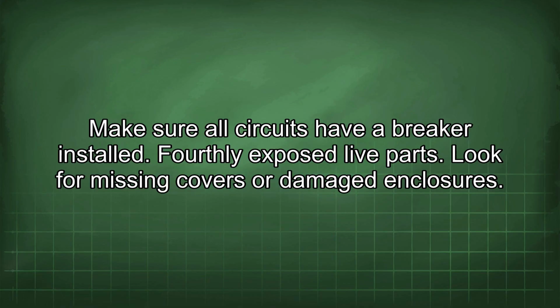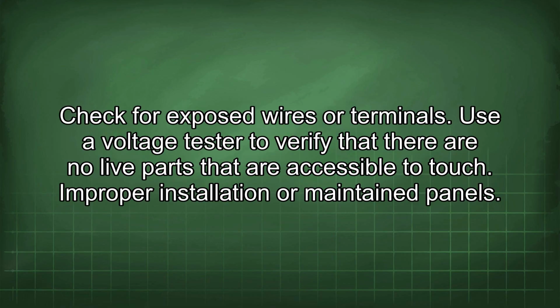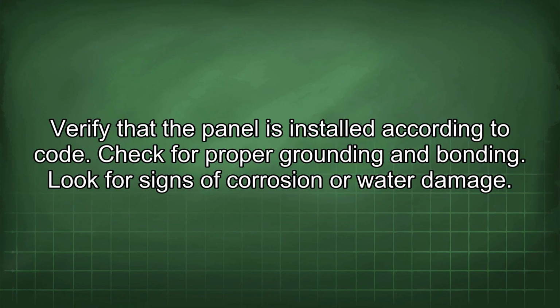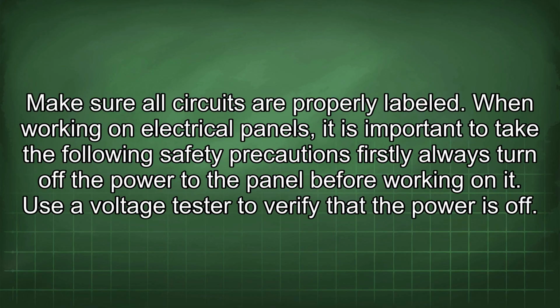Fourthly, exposed live parts. Look for missing covers or damaged enclosures. Check for exposed wires or terminals. Use a voltage tester to verify that there are no live parts that are accessible to touch. Improperly installed or maintained panels. Verify that the panel is installed according to code. Check for proper grounding and bonding. Look for signs of corrosion or water damage. Make sure all circuits are properly labeled.